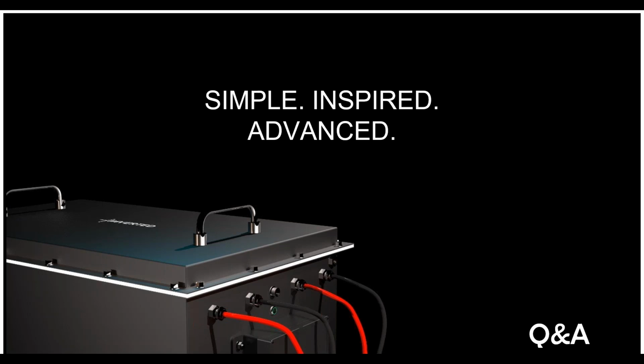The third consideration is what power sources you have - do you have EV, solar, battery, diesel generator? Depending on these multiple power sources, we determine which power source would be operating at what point. The fourth consideration is what technology you're using. For example, if you're using lead acid batteries, you size them assuming a depth of discharge of 50%, a charging current of C by 10, a discharging current of C by 10, an efficiency of 75%, and a certain space requirement.